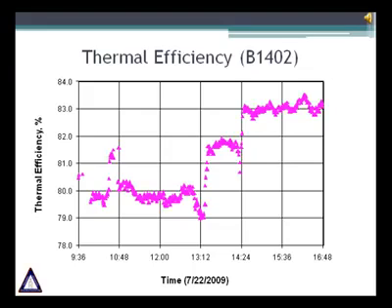In terms of savings, this means the following. This fired heater has a firing rate of about 100 MMBTU per hour. The price of each MMBTU is around $6. At the end of the year, the refinery will be saving more than $150,000 just for doing the adjustments already mentioned.